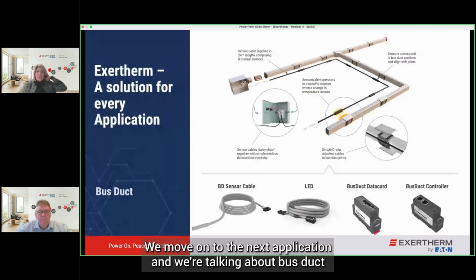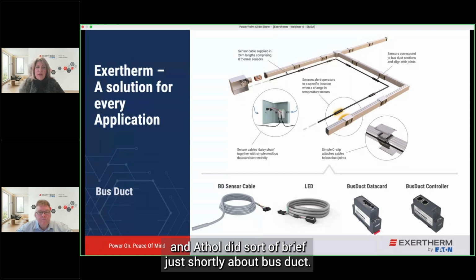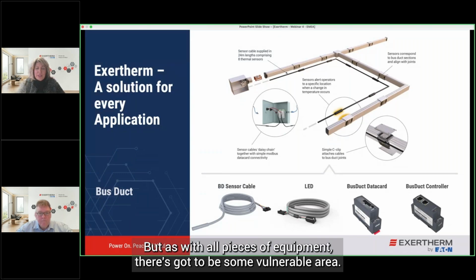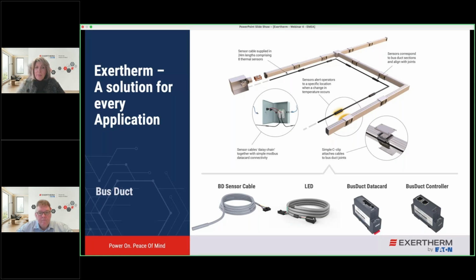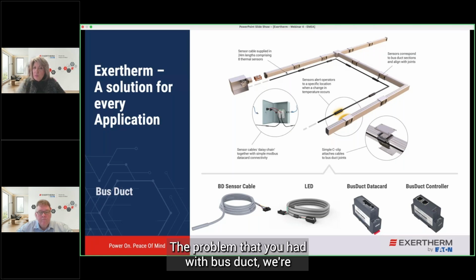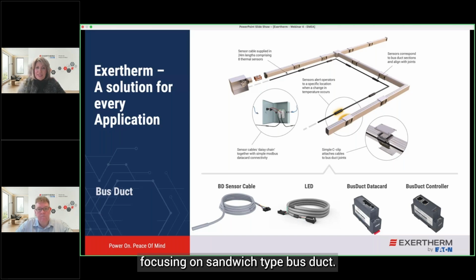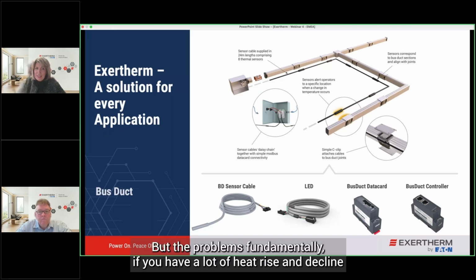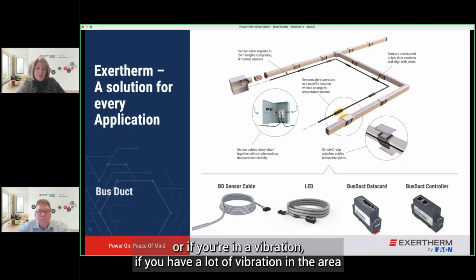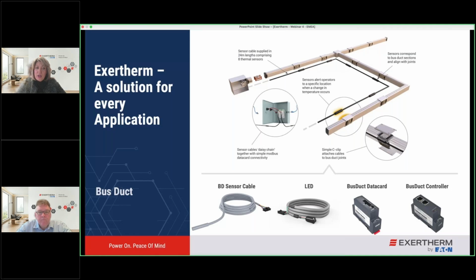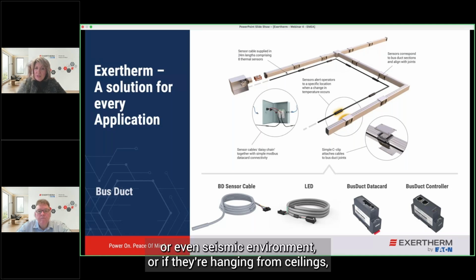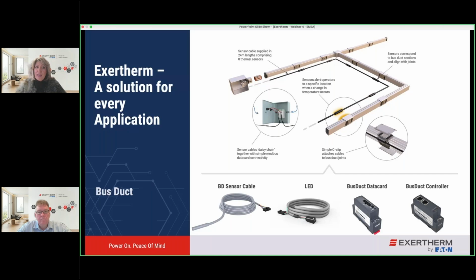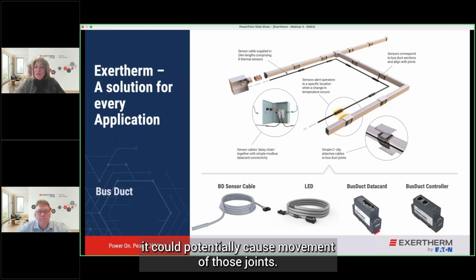We move on to the next application, and we're talking about busduct. Athol did brief you shortly about busduct, but as with all pieces of equipment, there's got to be some vulnerable area. The problem with busduct, and we're focusing on sandwich type busduct, is fundamentally that if you have a lot of heat rise and decline, or a lot of vibration in the area, or even a seismic environment, or if they're hanging from ceilings, it could potentially cause movement of those joints.